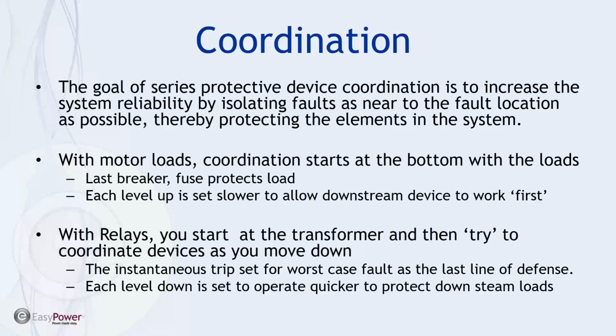Now, in the course of protecting transformers, and particularly the main transformer, you start by setting the relay to protect it, because it often can be the most expensive part of your system. And then in the case of motor loads, you want to have instantaneous trip close to the load, and then virtually no instantaneous trips in any device above it until you get to the main relay, because there you can predict what the worst case fault current will be and adjust accordingly.